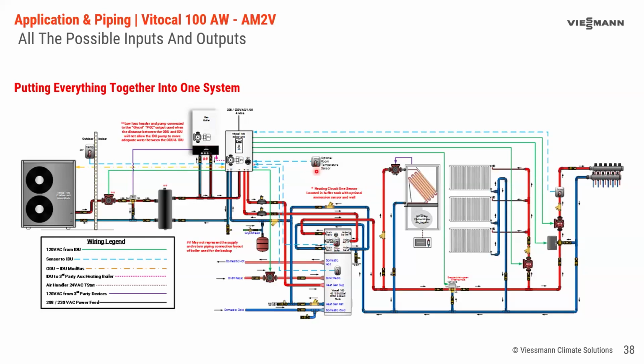So the room temperature feedback will help this buffer tank adapt to the room temperature, adjusting water temperature up or down based on the room set point. And we've also shown here the outdoor temperature sensor. The outdoor temperature sensor would hopefully be put on the north wall of the building, so it doesn't see the sun, northeast maybe, and it shouldn't be too close to the heat pump.